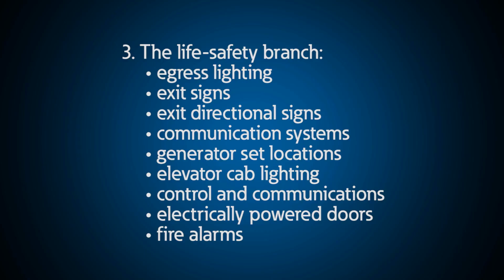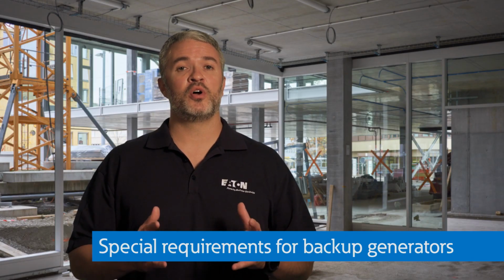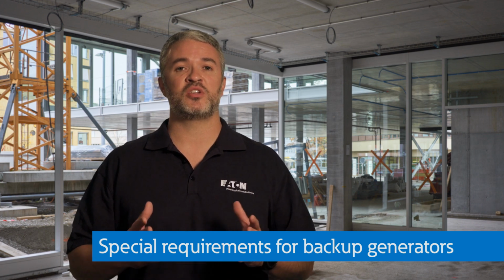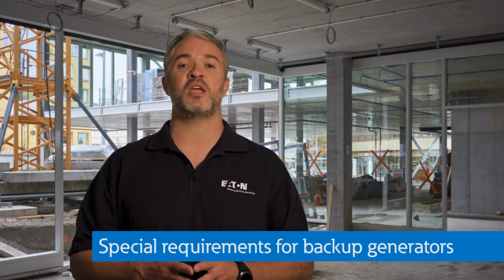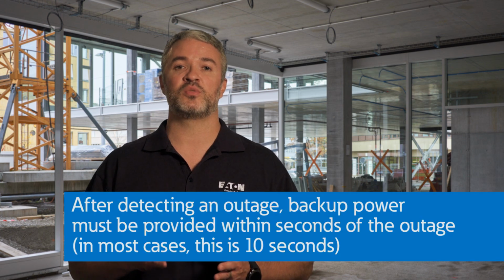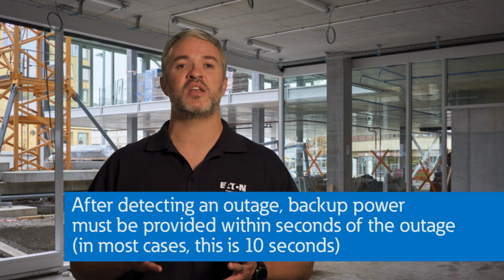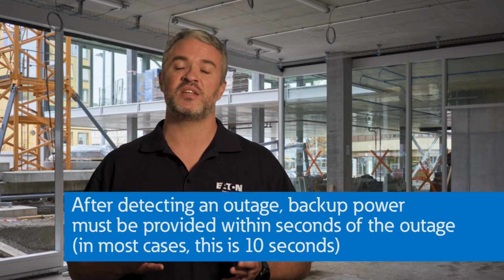It spans egress lighting, exit signs and exit directional signs, communication systems, generator set locations, elevator cab lighting, control and communications, electrically powered doors used for egress, and fire alarms and auxiliary functions of the fire alarm systems. Requirements of special note are those regarding generator backup for locations such as the operating rooms, critical care spaces, and medical labs. These requirements specify that after detecting a power outage, the generators must start and the transfer switches must transfer and restore power within a set number of seconds. In most cases, this is 10 seconds.